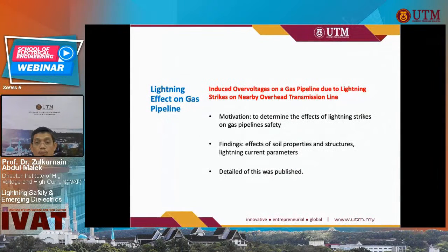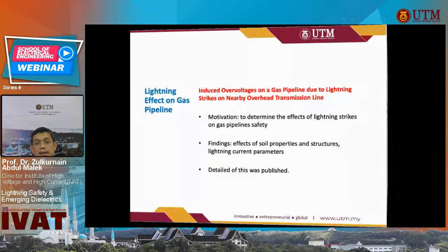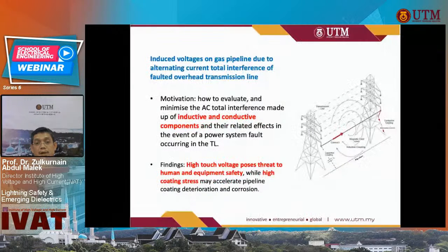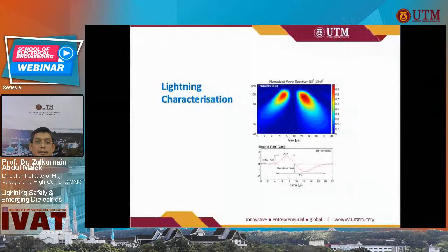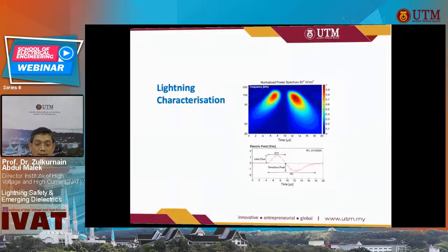Okay, we also do some studies on what happens if lightning strikes the ground and you have a gas pipeline nearby, what happens to the coating? And also if you have a short circuit due to a fault, for example, what happens again to the coating on the pipeline. So we do studies and publish these results. Another thing that we do regarding lightning is the characteristic of the lightning itself, and we can use certain tools to characterize lightning better.